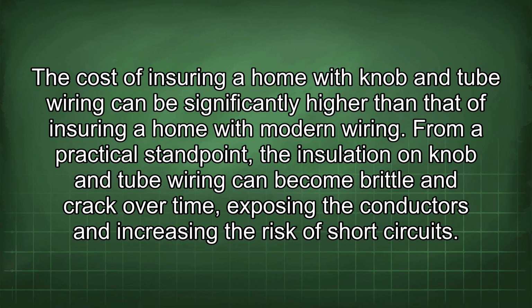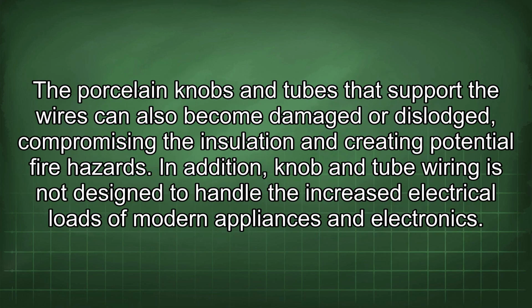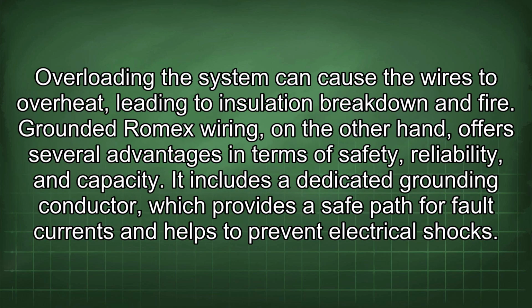From a practical standpoint, the insulation on knob and tube wiring can become brittle and crack over time, exposing the conductors and increasing the risk of short circuits. The porcelain knobs and tubes that support the wires can also become damaged or dislodged, compromising the insulation and creating potential fire hazards. In addition, knob and tube wiring is not designed to handle the increased electrical loads of modern appliances and electronics. Overloading the system can cause the wires to overheat, leading to insulation breakdown and fire.